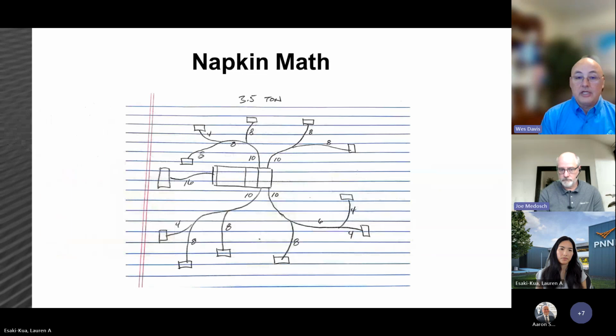Next is the duct design. We've got to make sure we get that conditioned air to the right spot. But unless I have a room-by-room load calculation and the blower table from the performance data, it's difficult to assess how much air I need to put in each room and then how large I need to make the duct to carry that air. How do I verify that this was done?